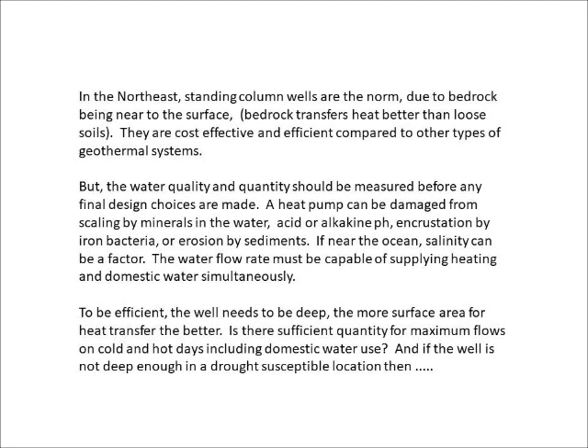The water flow rate must be capable of supplying water and heating simultaneously. To be efficient, the well needs to be deep. The more surface area for heat transfer, the better, is there sufficient quantity for maximum flows on cold and hot days, including domestic water use. And if the well is not deep enough in a drought-susceptible location, then it's certainly not going to work.